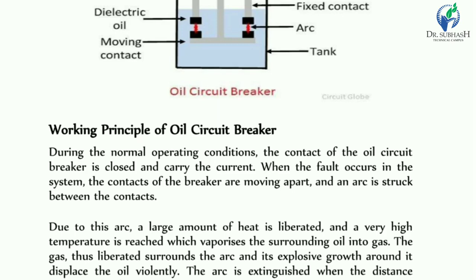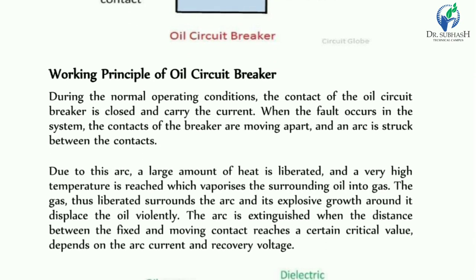The arc will be in contact with the surrounding oil and will be at high temperature. The high temperature causes the surrounding oil to vaporize into gas. The gas undergoes explosive growth and the oil is displaced. The arc is extinguished when the distance between the fixed and moving contact reaches a certain critical level.